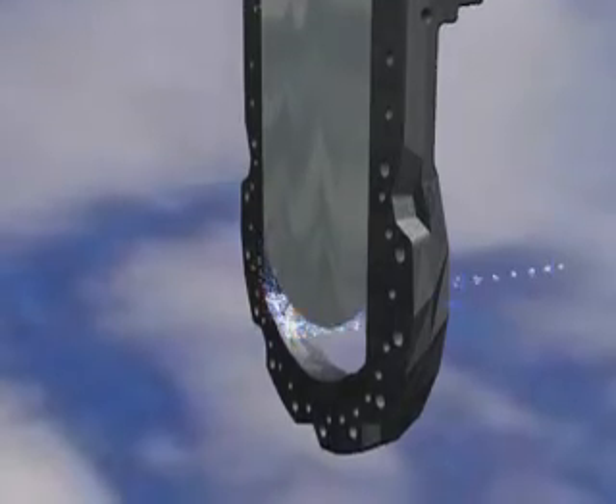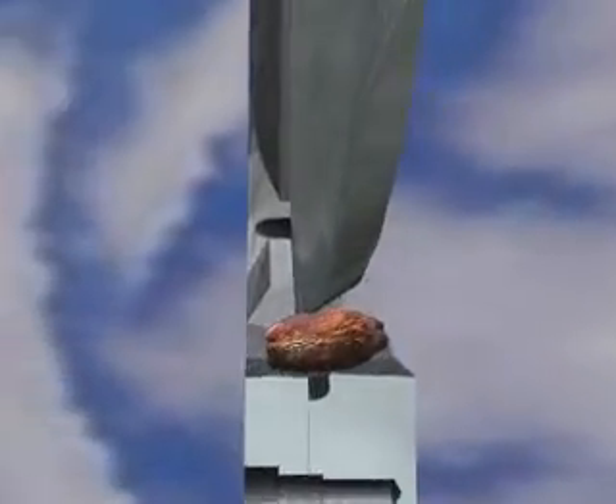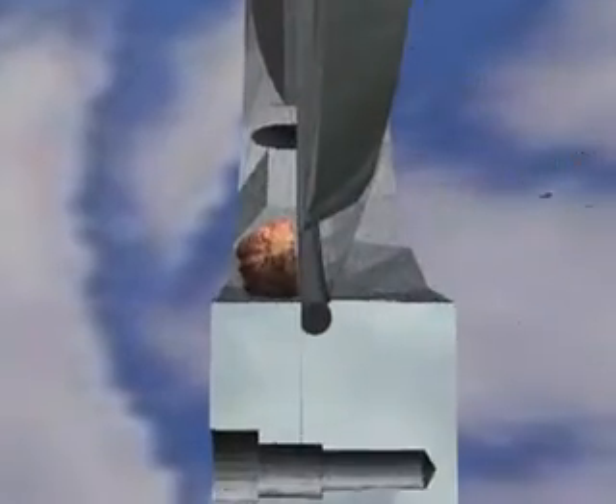As the Delta gate enters the closed position, three distinct actions occur. First, solids are displaced by the shearing edges of the gate and machine body. Secondly, the tip of the gate seats into the elastomer. Lastly, the beveled edge of the gate mates with the matching precision machined metal seat on the valve body and prevents the gate from over-compressing the elastomer seat.